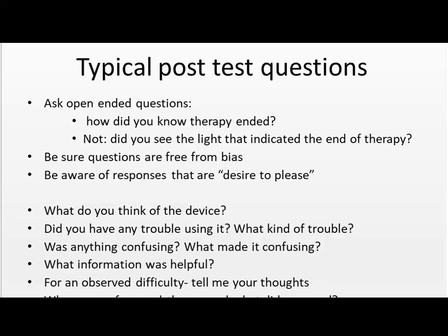Some typical post-test questions. They should be open-ended. You don't want to say, did you see the light that indicated the end of therapy? That's a yes-no question and leads the participant. You want to ask an open-ended question. How did you know therapy ended? And the participant would say he saw a light, indication light. Okay, good.